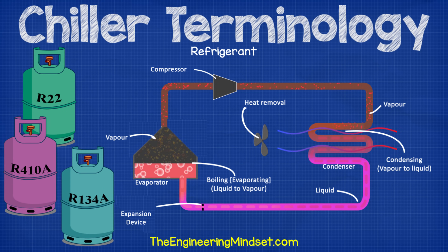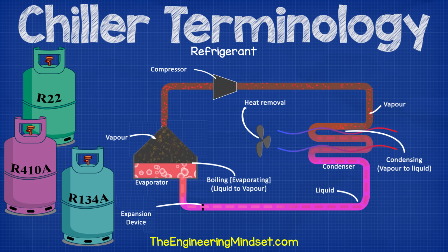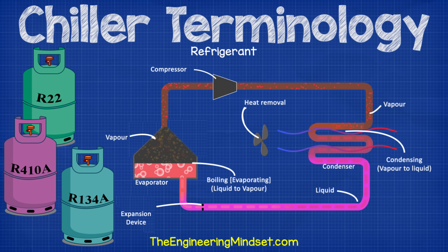Refrigerant. This is a specially designed fluid which moves around the inside of the chiller, collecting the unwanted heat from the evaporator and moving this over to the condenser so that the heat can be rejected from the building. It changes states between liquid and gas during the refrigeration cycle. It is moved around the chiller by the compressor. The refrigerant stays within the chiller and is always kept separate from the condenser water and the chilled water. Refrigerants will have strange names such as R134A, R1233ZD, etc.